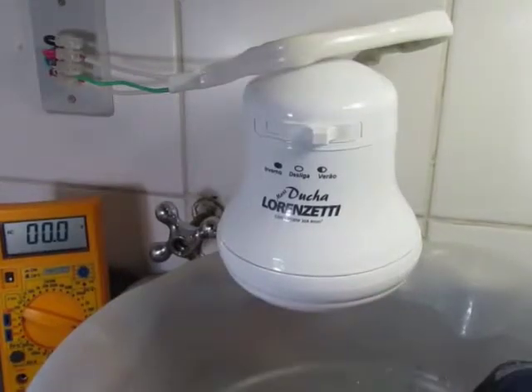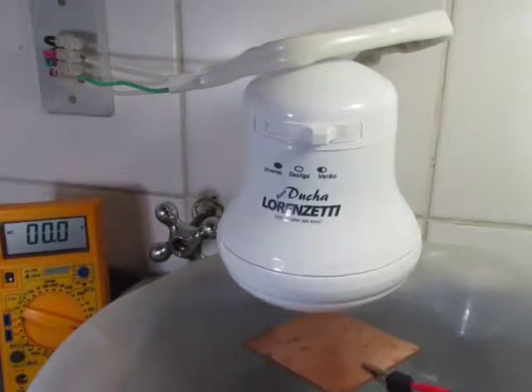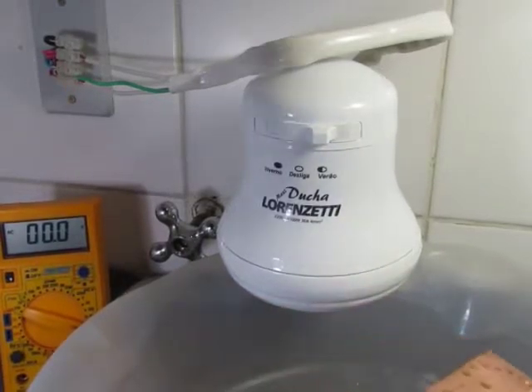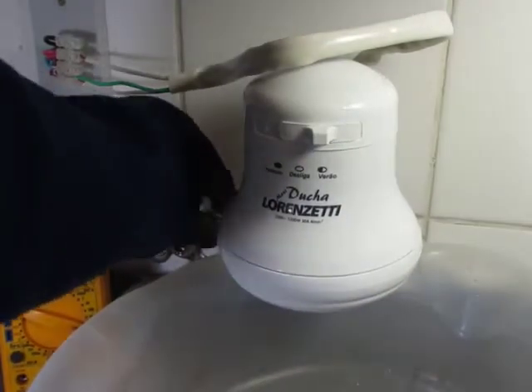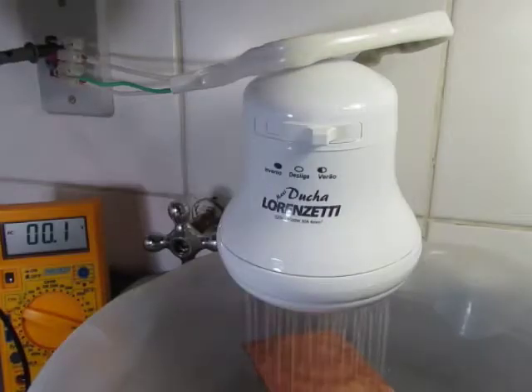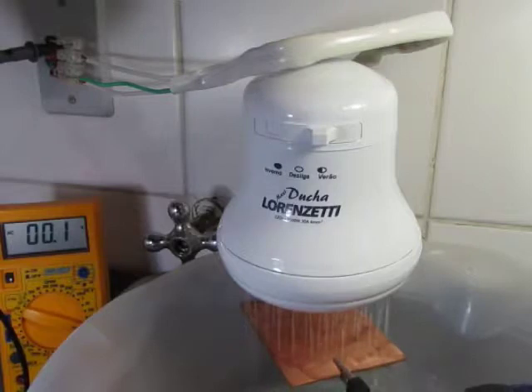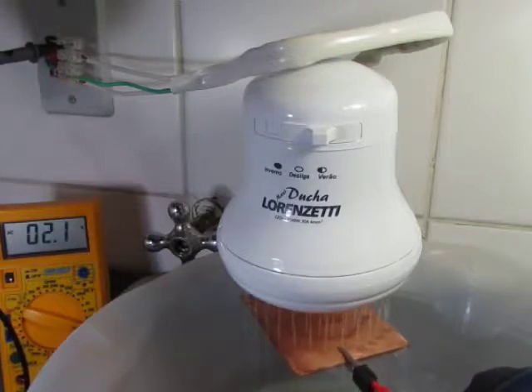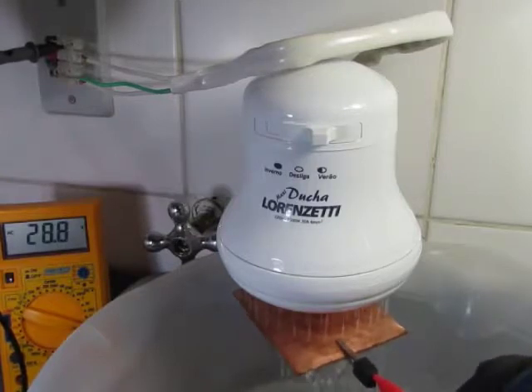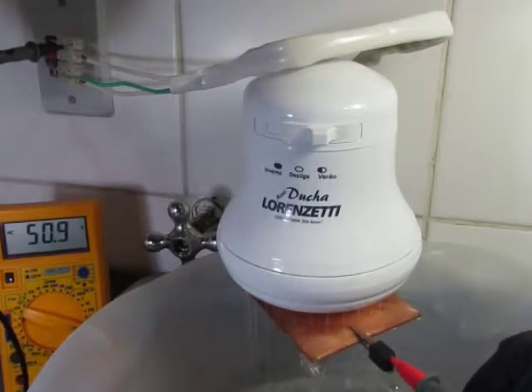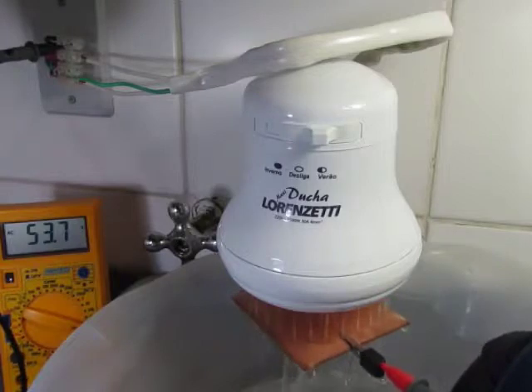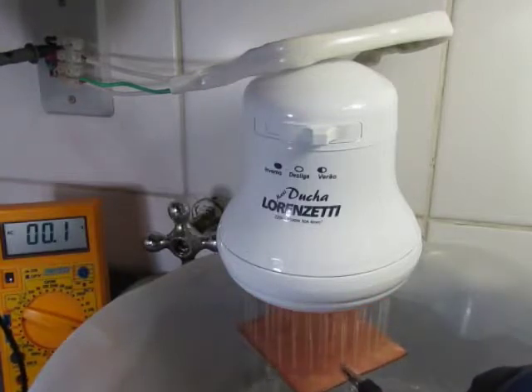Now I will place this copper-clad board closer and closer to the shower head like this and measure the voltage between the water and the mains ground. So here we go. Around 10 centimeters from the shower we have almost nothing, 3 centimeters, 4 volts, 2 centimeters, 10 volts. Now with the board touching the shower head we have around 50 volts. And as we move the board away the voltage disappears.